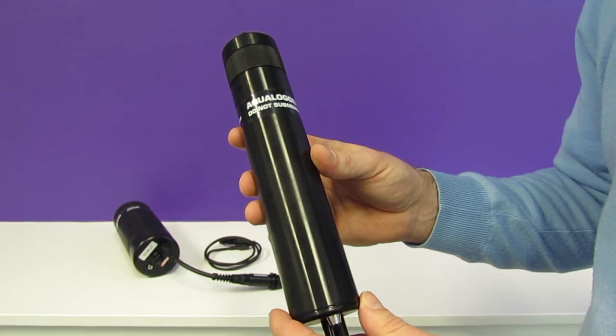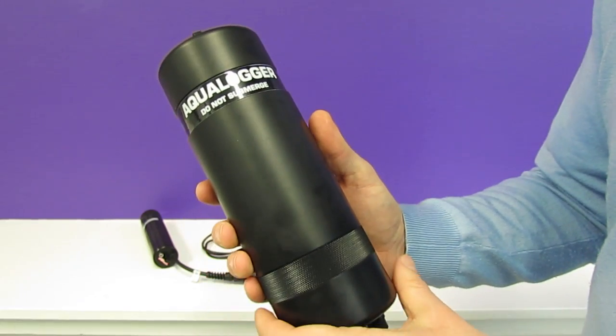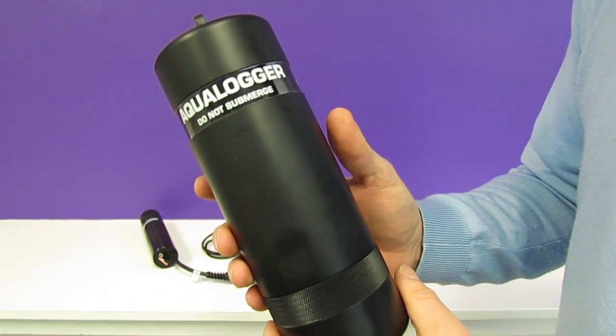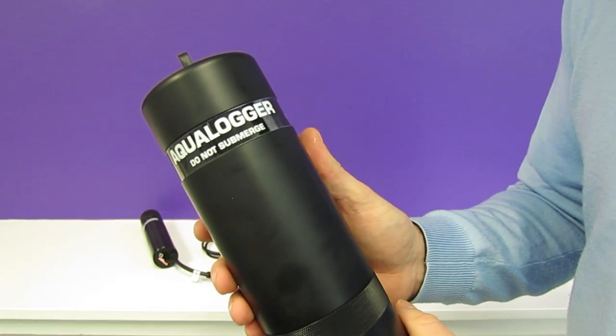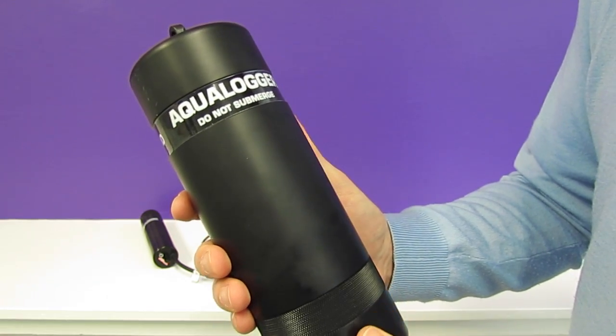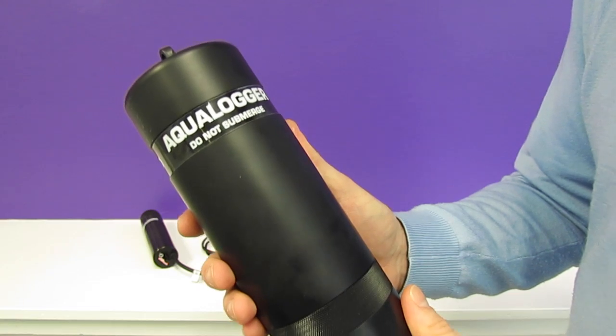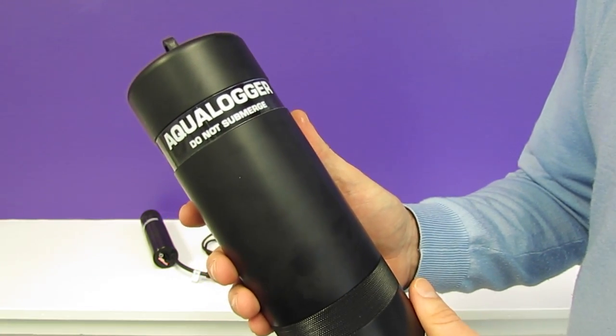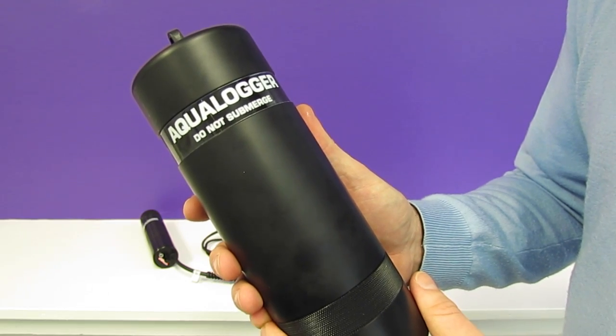This is the much larger aqua logger 7000. It's designed for use with the AP 5000 and AP 7000 aqua probes. The logger features a larger memory and larger battery capacity. Although it can still only record 15,000 data sets, those data sets are much larger than the data sets created from an AP 2000.